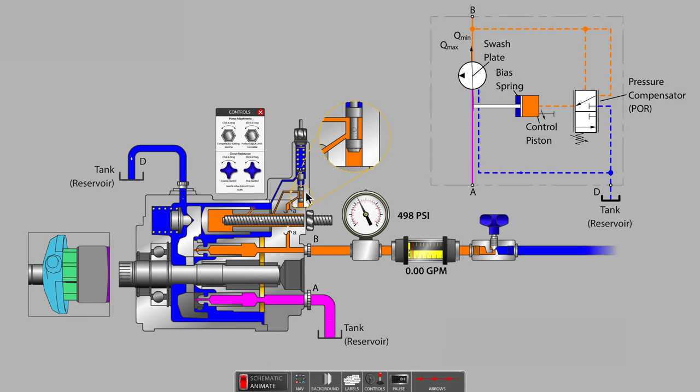In this system, we have a closed needle valve so we are ready to make the adjustment. With a pressure gauge available on the pump outlet line, simply turn the adjustment screw to compress the spring until the desired maximum system pressure is reached.